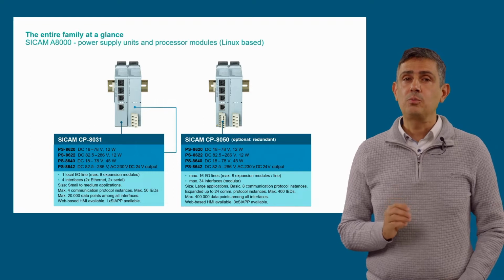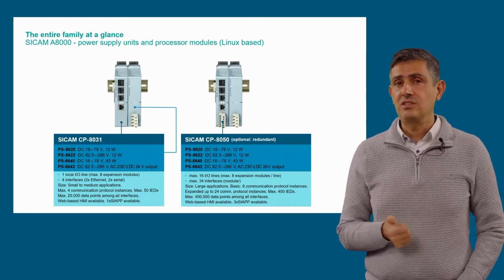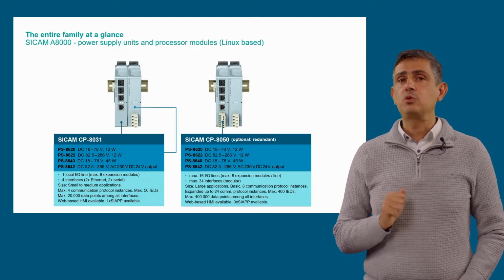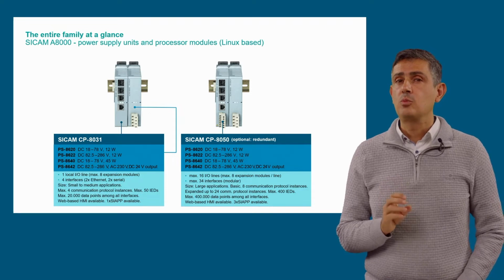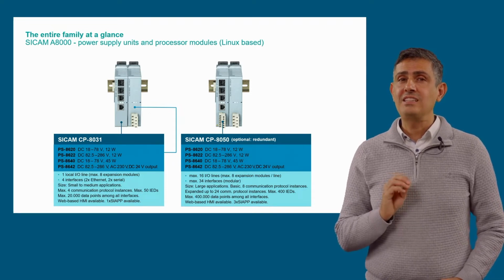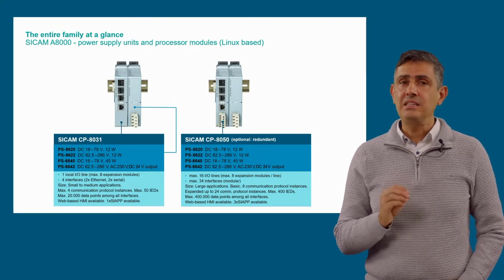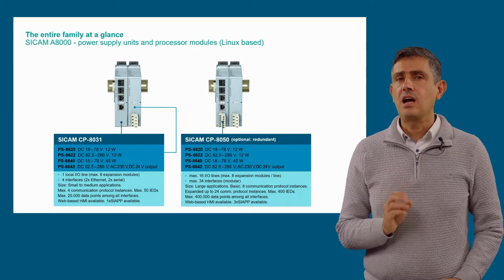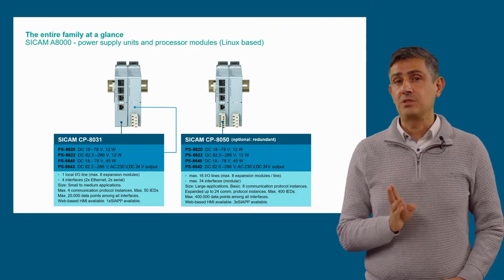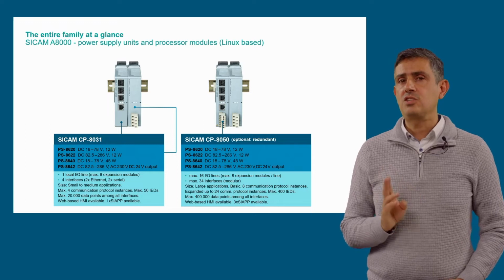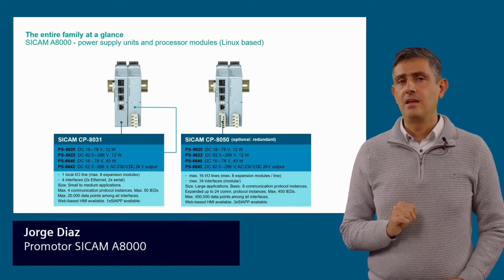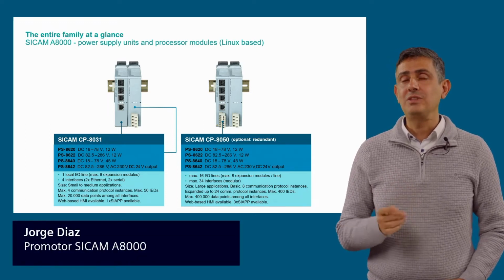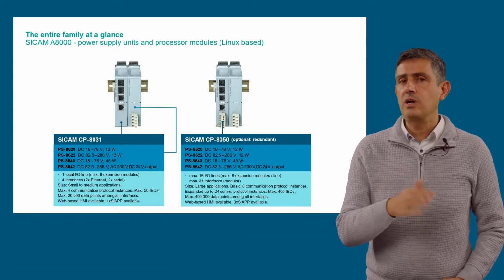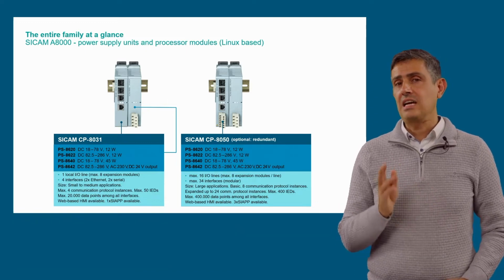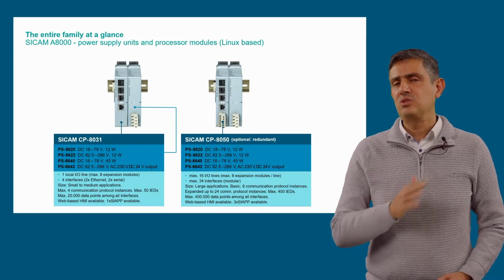In addition, it supports extra features such as device redundancy, can be expanded up to 24 protocol elements, supports the connection of I/Os of 19-inch rack type, has a built-in firewall, and can host up to 3 user-defined SIAPs. Also, the web-based HMI feature is included here. This CPU can be powered up with the same power supplies used for the smaller RTUs, so the amount and types of spares required can be reduced to a minimum.